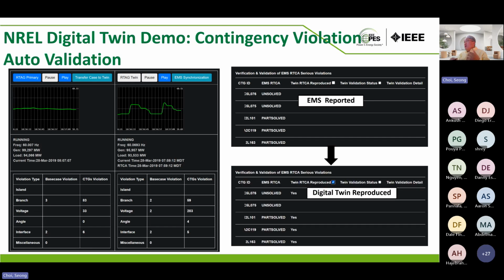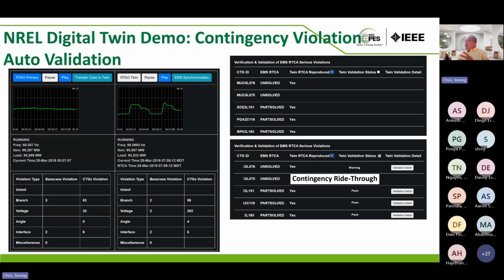With the digital twin, we're able to reproduce those contingencies. The EMS reported two of them, but the digital twin validated only one as reproducible, so operators can ignore the one that wasn't reproduced in the digital twin. Then the digital twin, with generation redispatch and other changes, is able to solve the unsolved contingency. So using the digital twin, we show how we can ride through the contingencies. Operators currently have to do this all manually, but now with a digital twin, you can do it in an automated way.